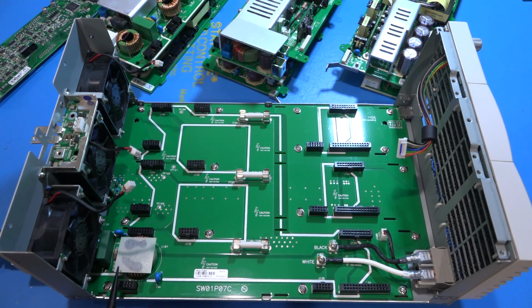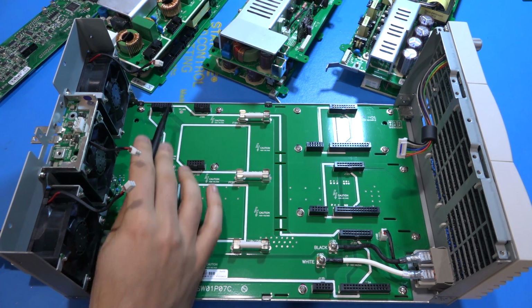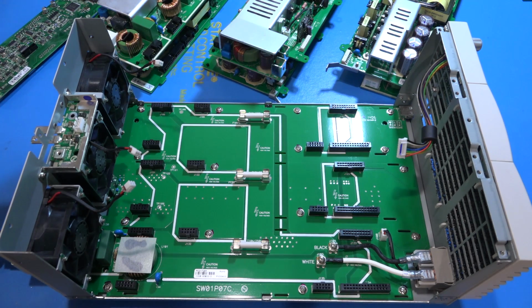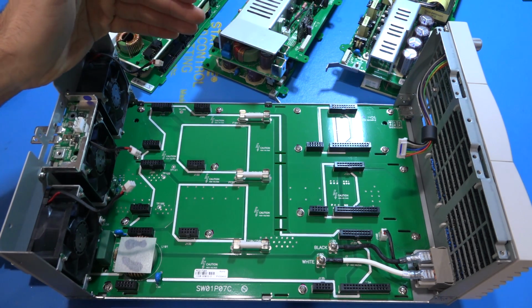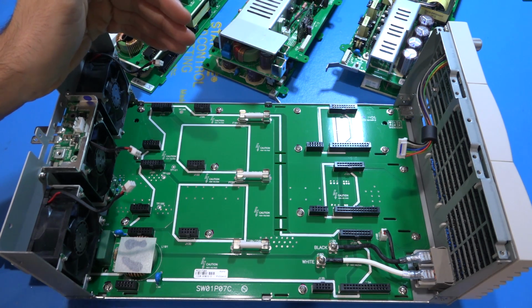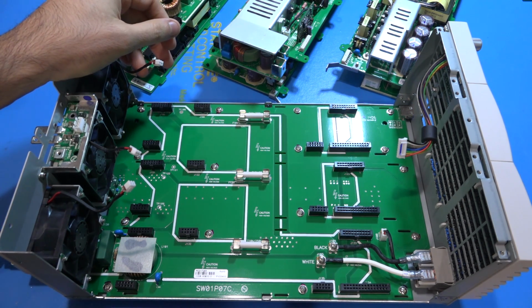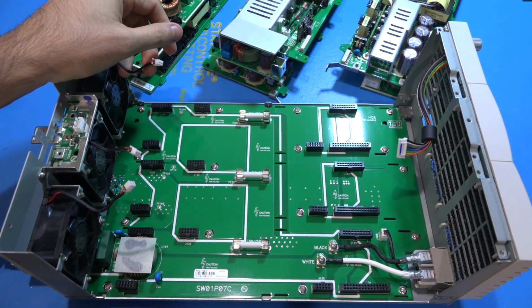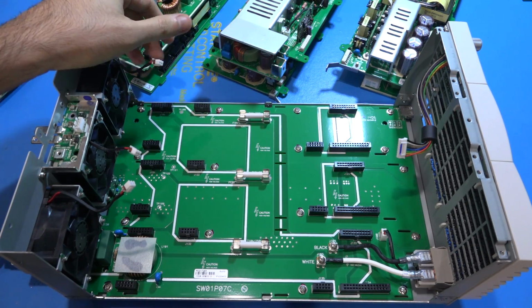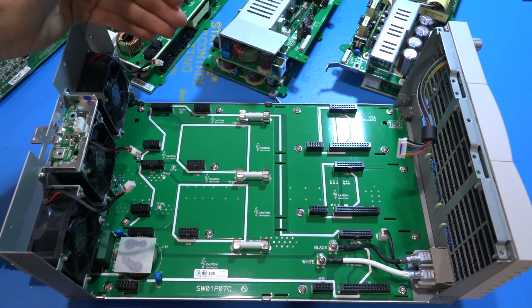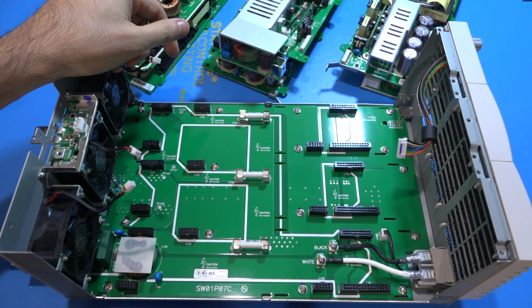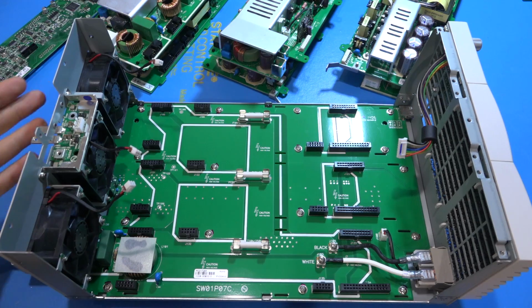AC line comes in, filtering at the front, then goes to the front switch. This switch has electronic trip built into it, and the line voltage is placed onto these connectors, allowing AC to go into one of the two boards of each power supply. That board is primarily responsible for the main rectification, with switching networks, soft start and so on, putting out the main rectified voltage, around 360 volts here in the United States, onto the main bus. The other module that plugs in picks up that voltage, does the main DC-DC conversion, and provides the main output of the power supply going to the back, taken from the top.